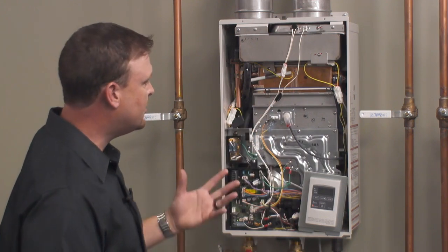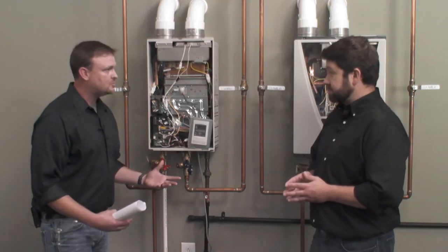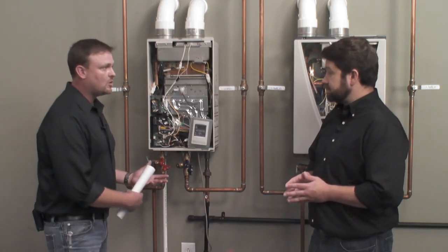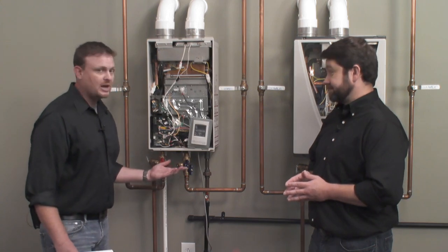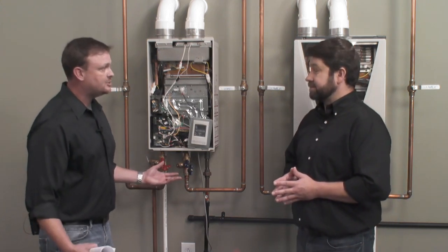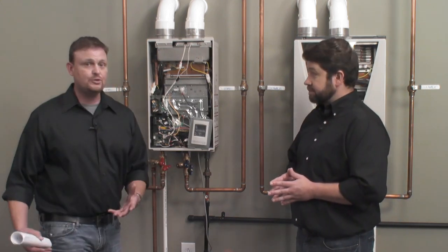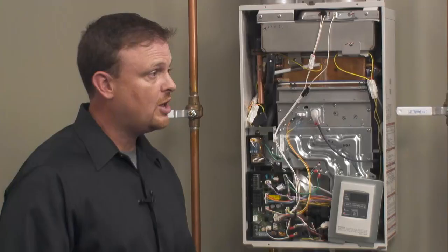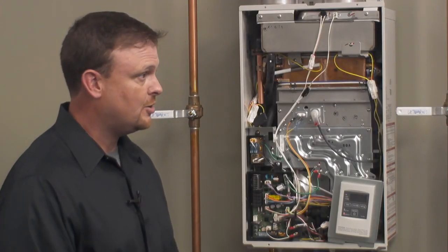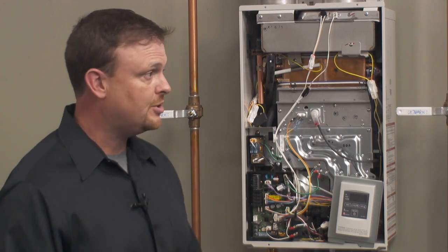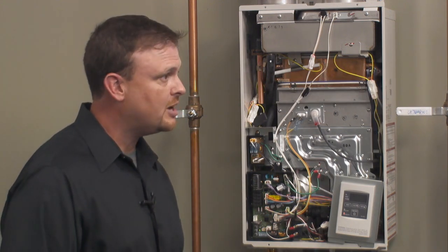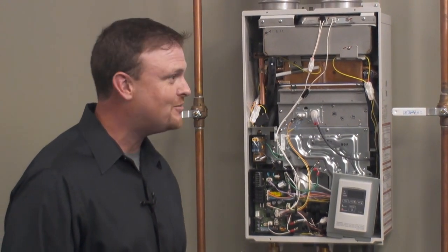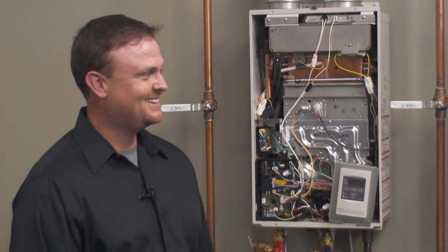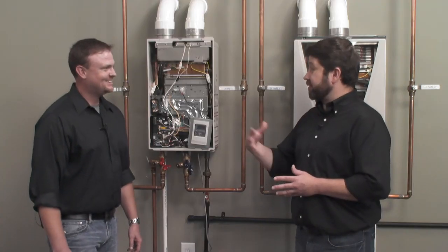One of the things that we like to talk about as well, whenever you're putting in these water heaters, is that a good option is to have isolation kits. You need isolation kits because from time to time you're going to have to do work on the water heater. You'll have to de-lime it, you'll have to do any kind of maintenance on it. So you're going to have to be able to isolate the water heater. And if you don't have this, it becomes a problem a little bit. It can make your day, especially after the fact, if you're doing service or troubleshooting, a lot more difficult.